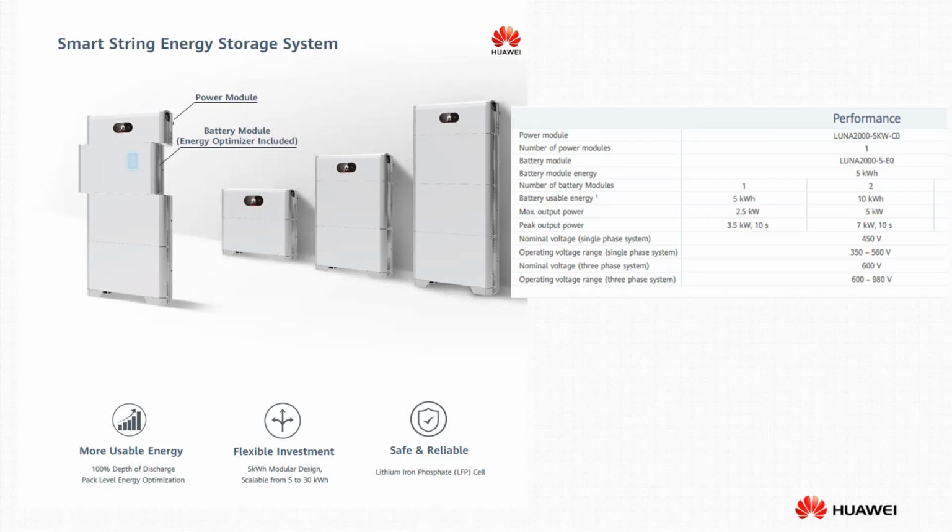The nominal voltage of the battery module is 51.2 volt like a normal battery, but the power module is responsible for stepping that voltage up to around 600 to 980 volt, which is the operating range of the system for the inverters. For every installation you would need one battery module and a power module. One power module can take up to three battery modules, so you can build up to 30 kilowatt hour of battery system in multiples of 5, since one battery module is 5 kilowatt hour.